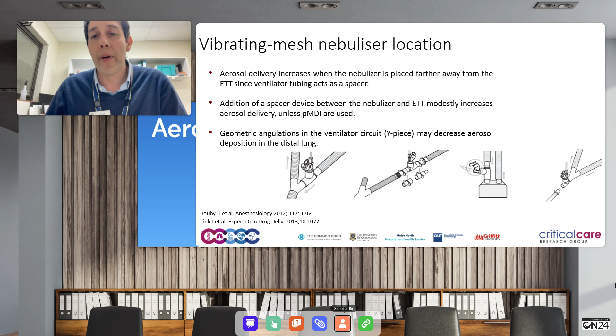If you use, for instance, an elbow connection before the endotracheal tube, sometimes you have a problem with the position where the angulation lies, because you need to have a straight circuit into the endotracheal tube to achieve the best deposition. This is a clear study from a very distinguished group led by Fink that clearly demonstrated, in the blue bars, the use of the vibrating mesh nebulizer, and it's clearly demonstrated that when you are a little bit closer to the endotracheal tube, like in this case, you are going to have a little bit less drug deposition because you need to be far away from the endotracheal tube.